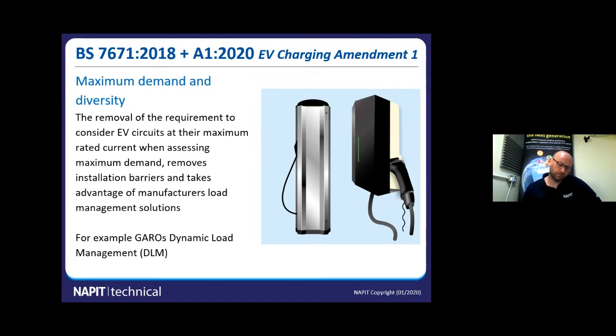Thanks, Paul. Yeah, we have a great solution for dynamic load management. With our solution in a domestic environment, we would install a meter at the head of the installation, which would communicate back to the charge point on a built-in cable. It's a Modbus communication. From that point, the charge point can see exactly the total load of the home. So it'll take into consideration showers, cookers, lighting circuits, and as the load rises within the home, the charge point will then automatically reduce itself. It won't turn off, but it will reduce itself down to a safe load.